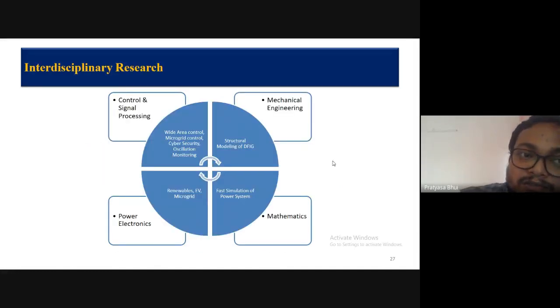Now there are so many interdisciplinary research scopes where you can collaborate with control and signal processing, and wide area controls. Like in damping controls, generally we use local measurements, local power flow, frequency or generator speeds, and then try to control the active power of the generators. But you can use wide area control, where a measurement from another location will be used to get the control action.